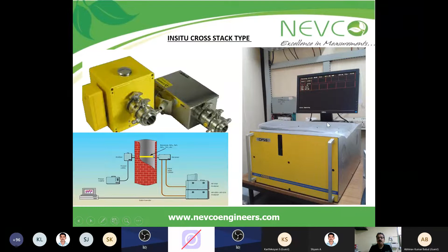When the light passes from the emitter, you switch on the lamp inside, and there's a mirror on the other side. That's why these two are fixed 180 degrees from each other. From them, an optic fiber cable carries the light to the spectrometer. This is the actual figure of the spectrometer, which has a built-in computer and a keyboard connected directly to get the measurement.